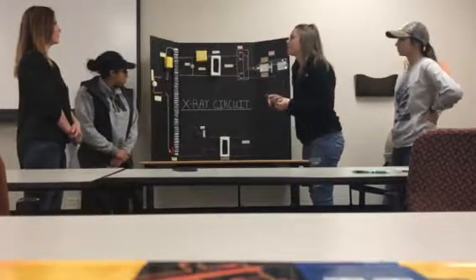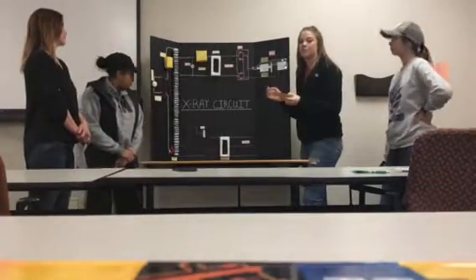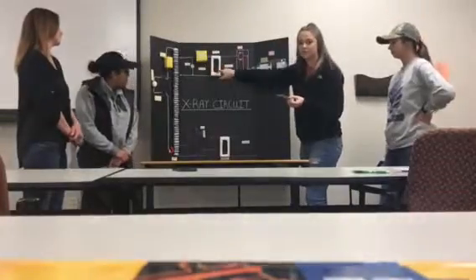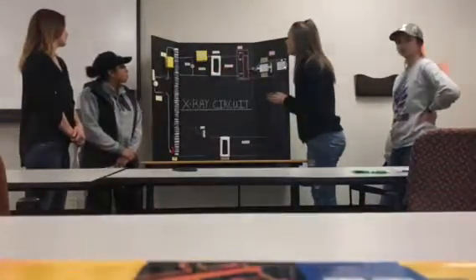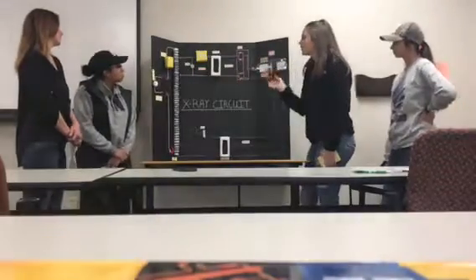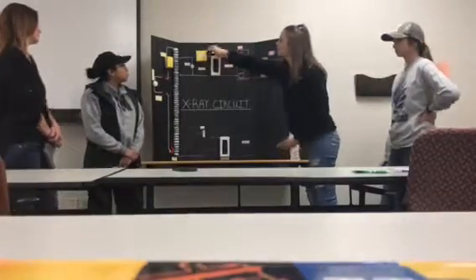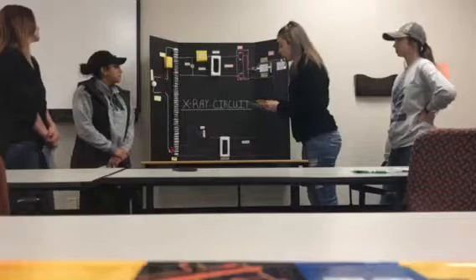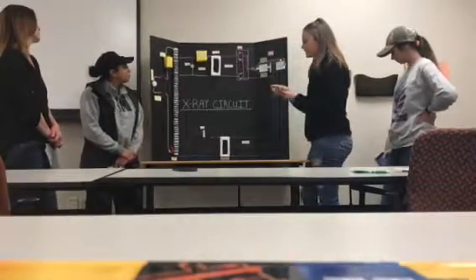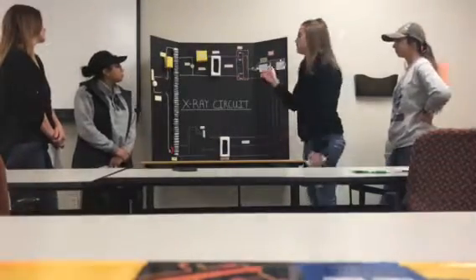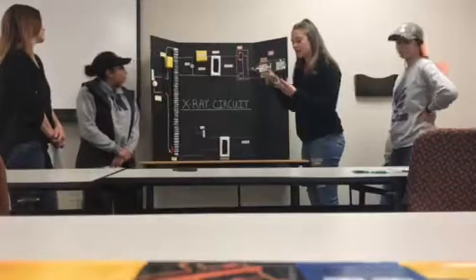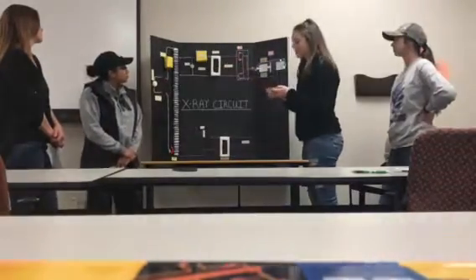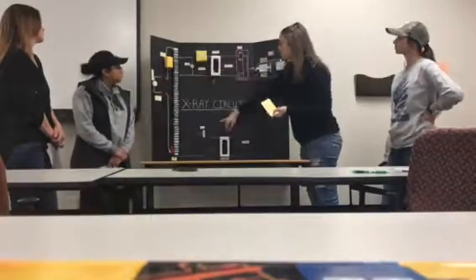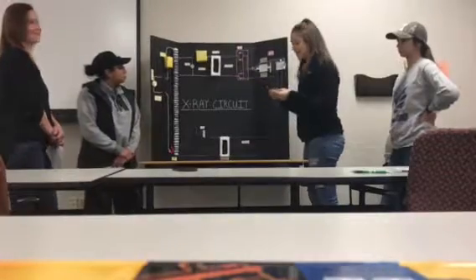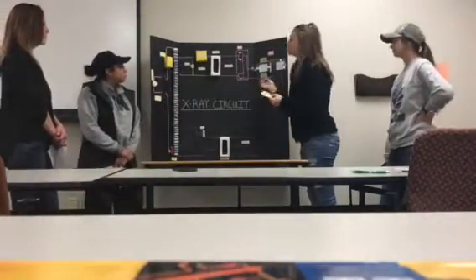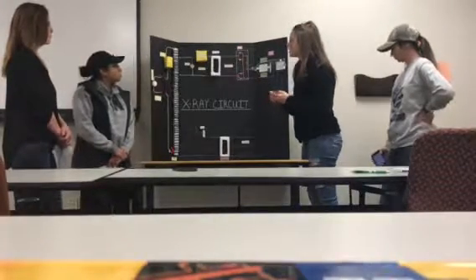And the primary purpose of the auto transformer is to provide a voltage that will be increased by the step-up transformer here to a kilovoltage. And the KVP meter is what's going to be monitoring the voltage. And then we're going to go to the exposure timer, which is on the primary circuit because it's easier to control a low voltage rather than a high voltage. So that's why we're going to discuss it here instead of over here. There are many different variations of it, but its main job is to work with the rheostat, which Danielle will talk about later. Together they determine the quantity of electrons boiled off the filament and available for X-ray production.